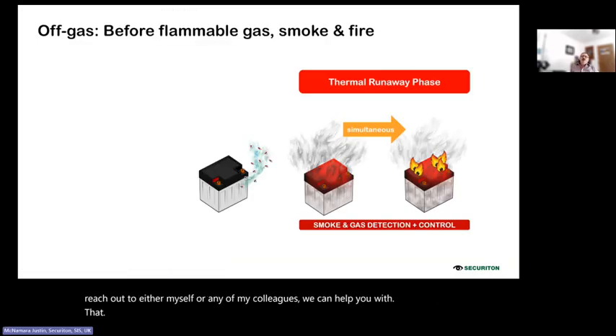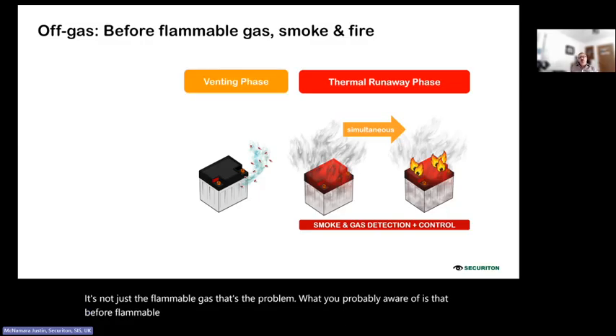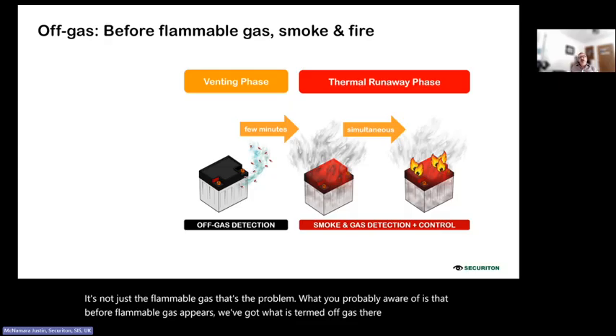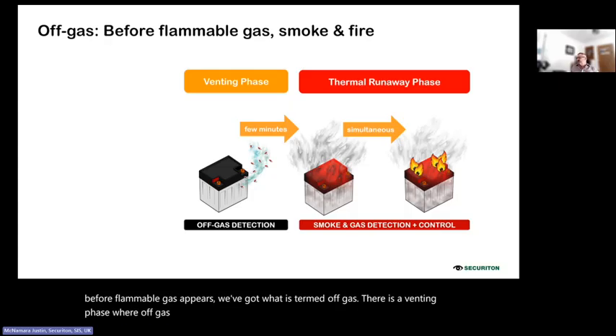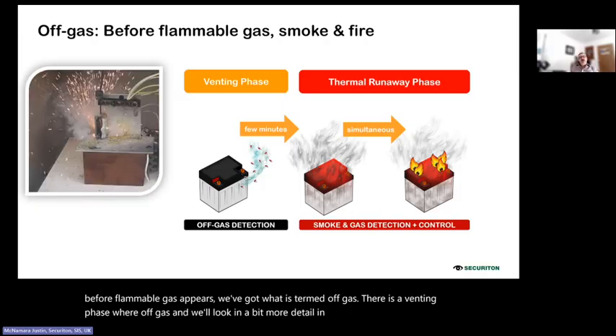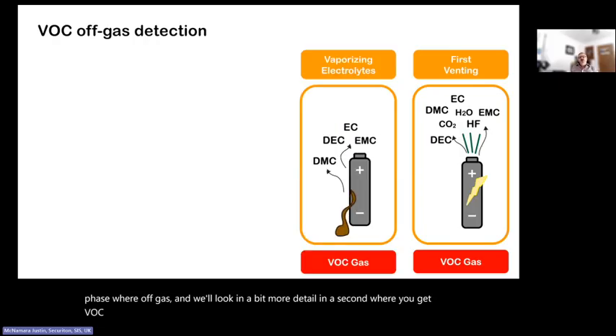It's not just the flammable gas that's the problem. What you're probably aware of is that before flammable gas appears, we've got what is termed off gas. There is a venting phase where off gas, and we'll look in a bit more detail in a second, where you get VOC gases, volatile organic compounds. There are some examples here on screen.